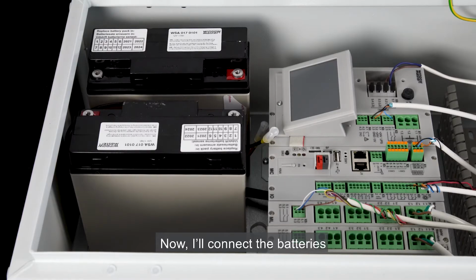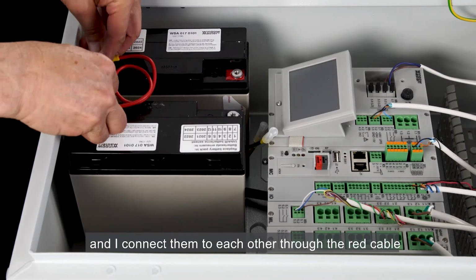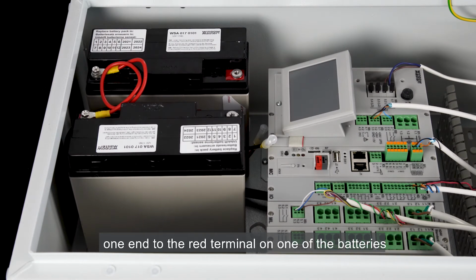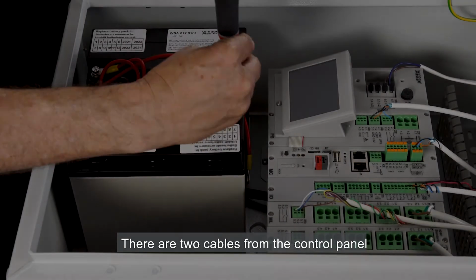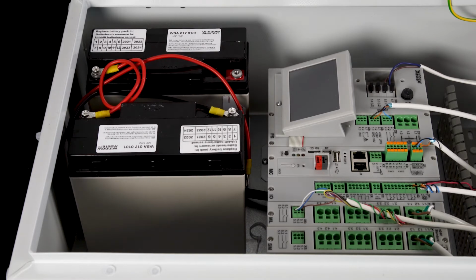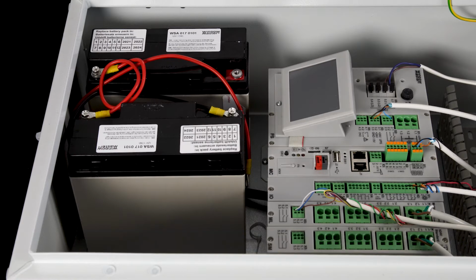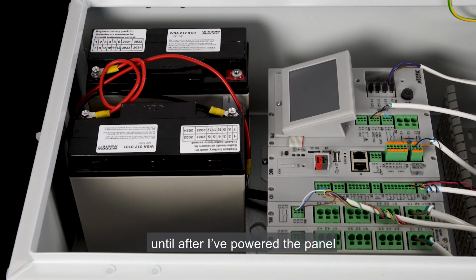Now I'll connect the batteries. Place them inside the panel and I connect them to each other through the red cable, one end to the red terminal on one of the batteries and the other to the black terminal on the other battery. There are two cables from the control panel that need to be connected to the batteries. The black cable is connected to the remaining black terminal. I'll wait with connecting the red cable to the remaining red terminal until after I've powered the panel.